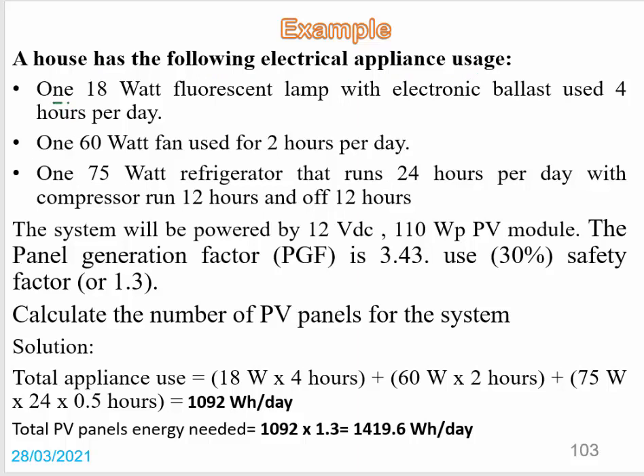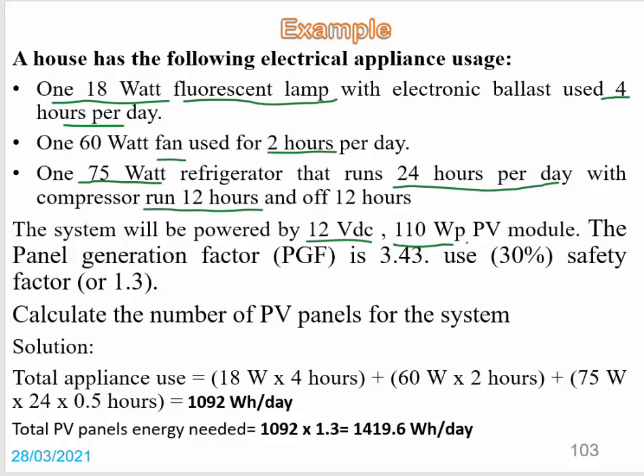Here we have an example. A house has the following electrical appliances: one 18-watt fluorescent lamp used 4 hours per day; a 60-watt fan used 2 hours per day; and a 75-watt refrigerator that runs 24 hours per day, but with the compressor running only 12 hours. So effectively, we treat the refrigerator as working for 12 hours. The system is powered by a 12V DC, 110-watt peak PV module.